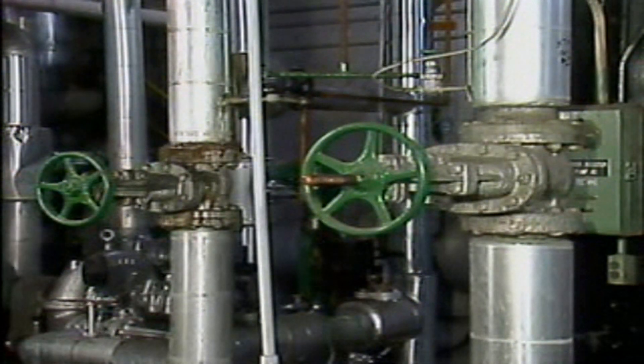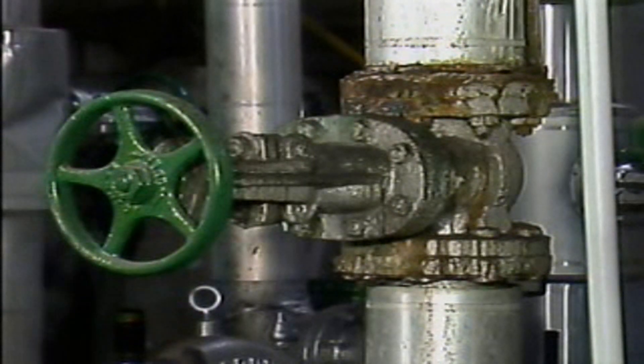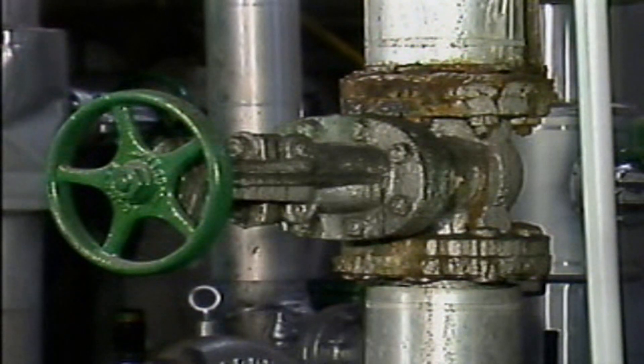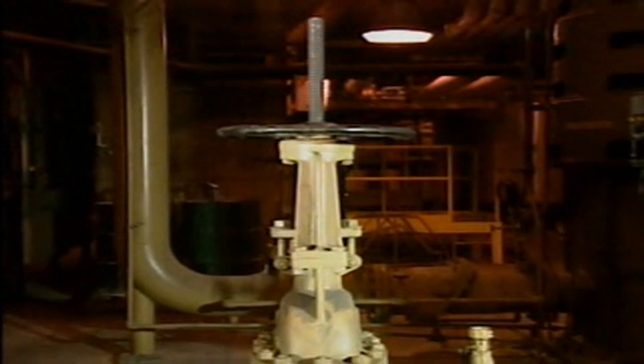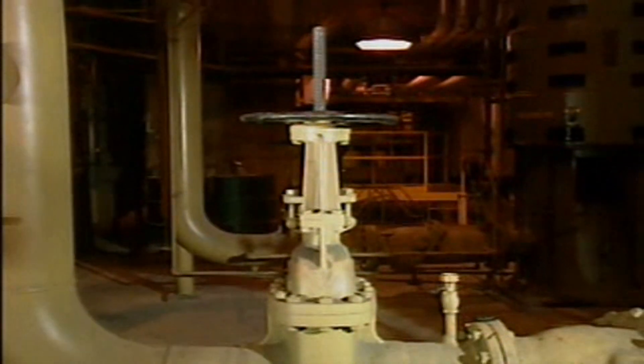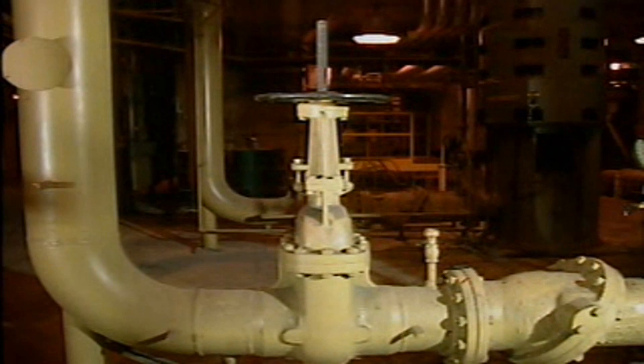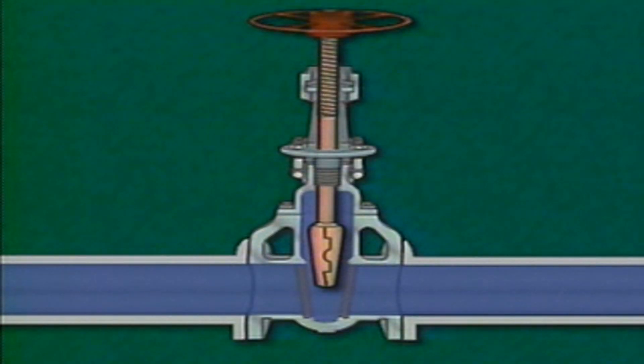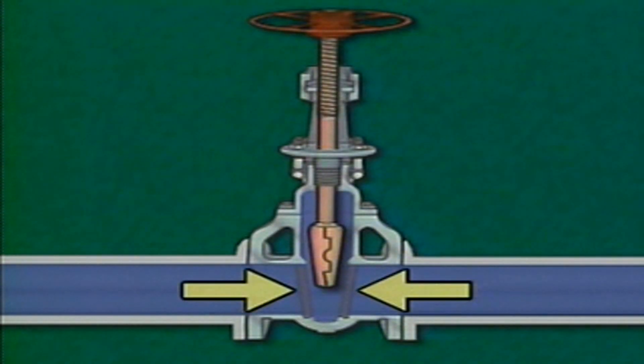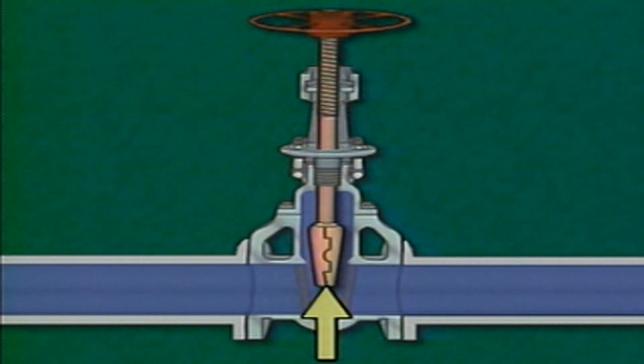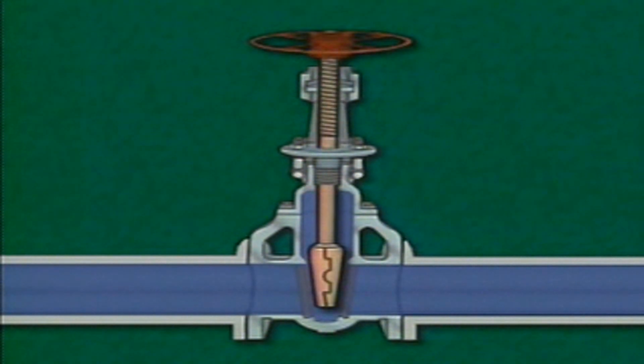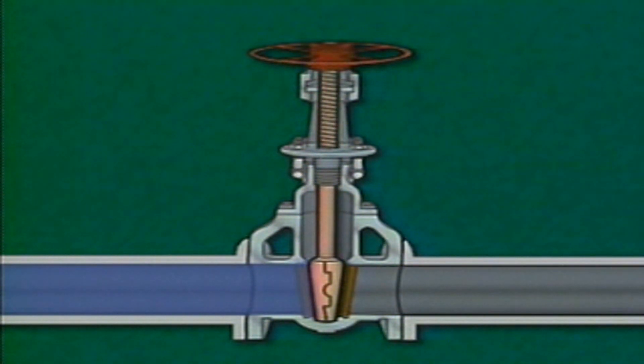Gate valves are primarily used for turning fluid flow on and off and for isolating equipment. They're normally installed in applications where straight flow is desired. A gate valve generally has a relatively long body and stem, which extends some distance beyond the piping that the valve is connected to. A gate valve typically has two seating surfaces and a disc that fits between them. The disc is raised and lowered, like a gate, to start or stop the flow of fluid through the valve.